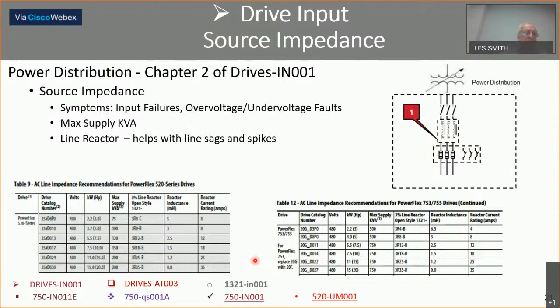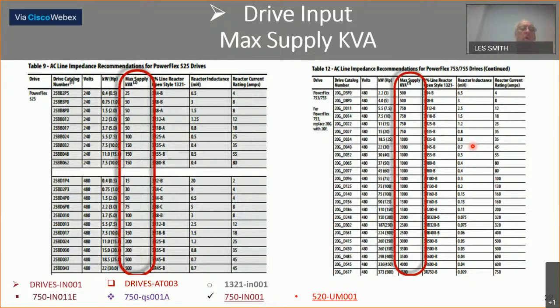Okay, we're using the grounding and bonding drive installation book here. It will have tables in it for you. And the tables will relate to the specific vendor drive that you're using, and give you guidelines for when to use, for instance, reactors, filters, etc. And that is right here after the reactor and before going into the drive. More specifically, right here, we're going to look at the PowerFlex 525 drives and the PowerFlex 753, 755 drives.